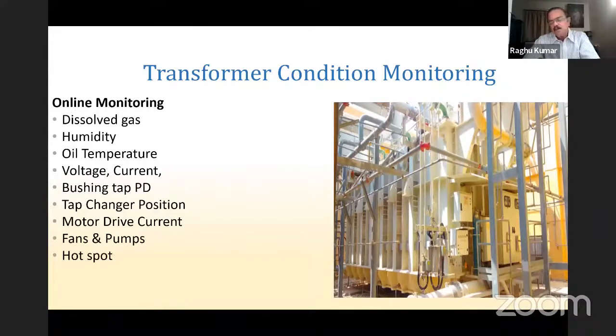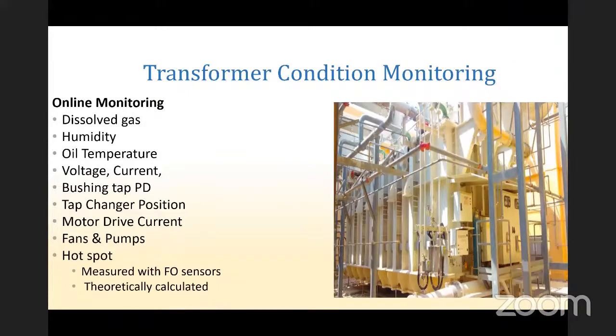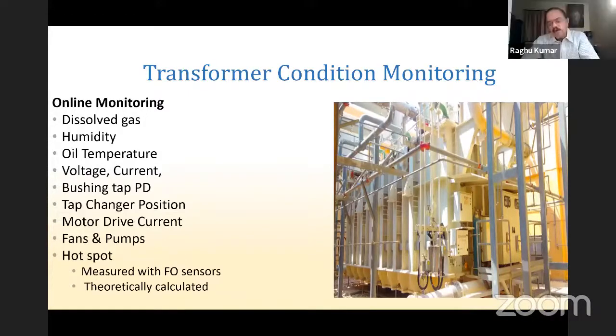And hotspots: there are two ways of finding out the hotspot. One is theoretical calculation. Second is physical sensors kept inside the transformer. Fiber optic sensors are kept inside the transformers, and from these, direct hotspot temperatures are measured. So these are the basic online monitoring systems.